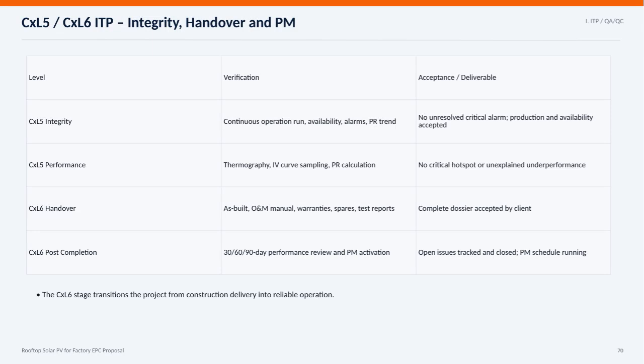At the CXL5 level, we focus on integrity and performance verification. This includes monitoring continuous operation, checking for alarms, and analyzing the performance ratio trends to ensure there are no unresolved critical alarms and that production meets expectations. Additionally, thermography and IV curve sampling help confirm there's no critical hotspot or unexplained underperformance.